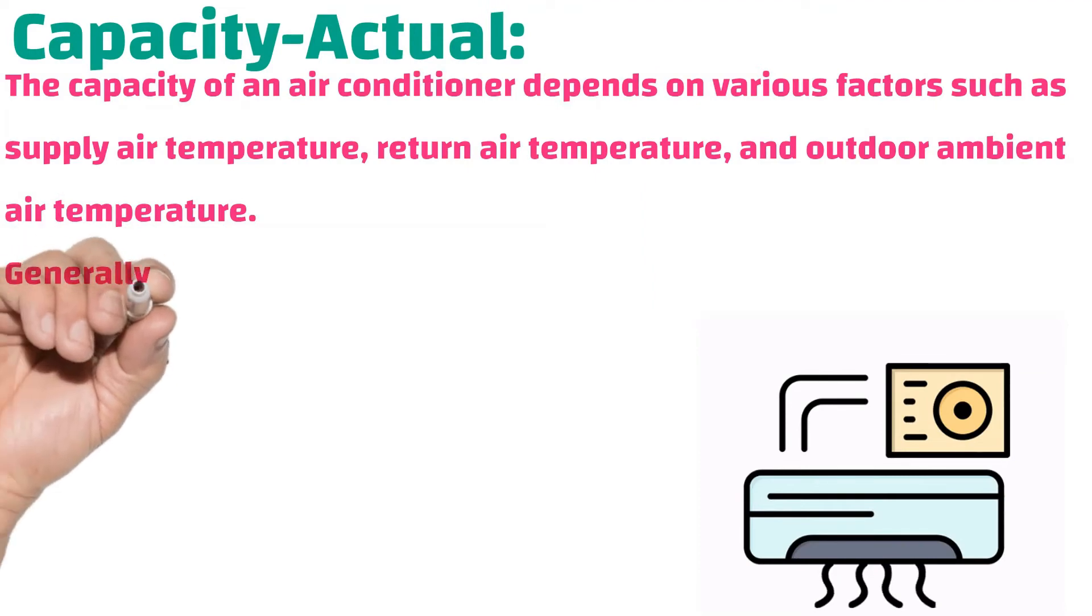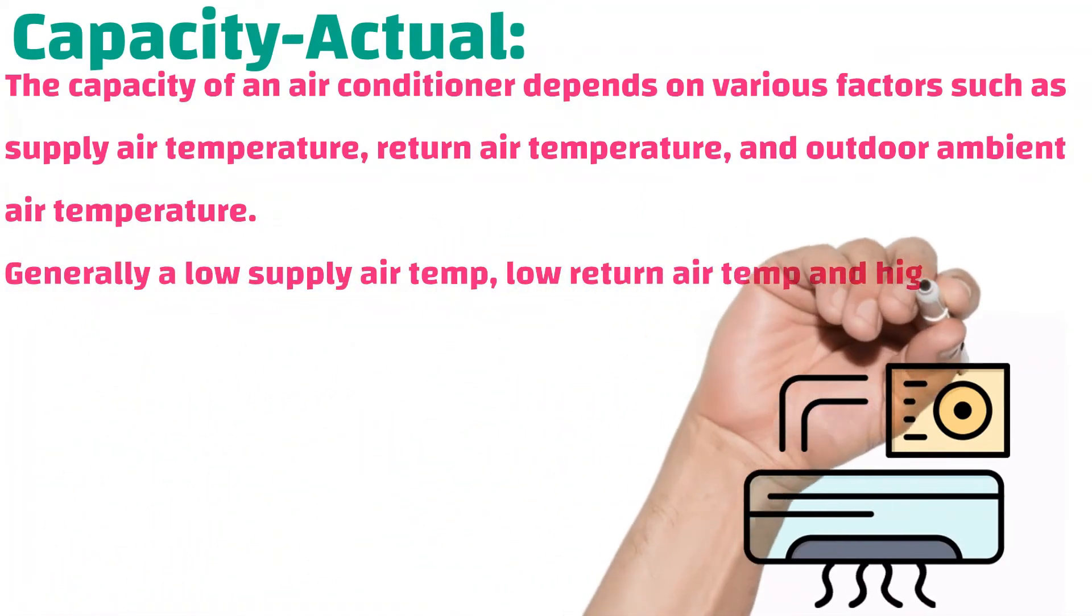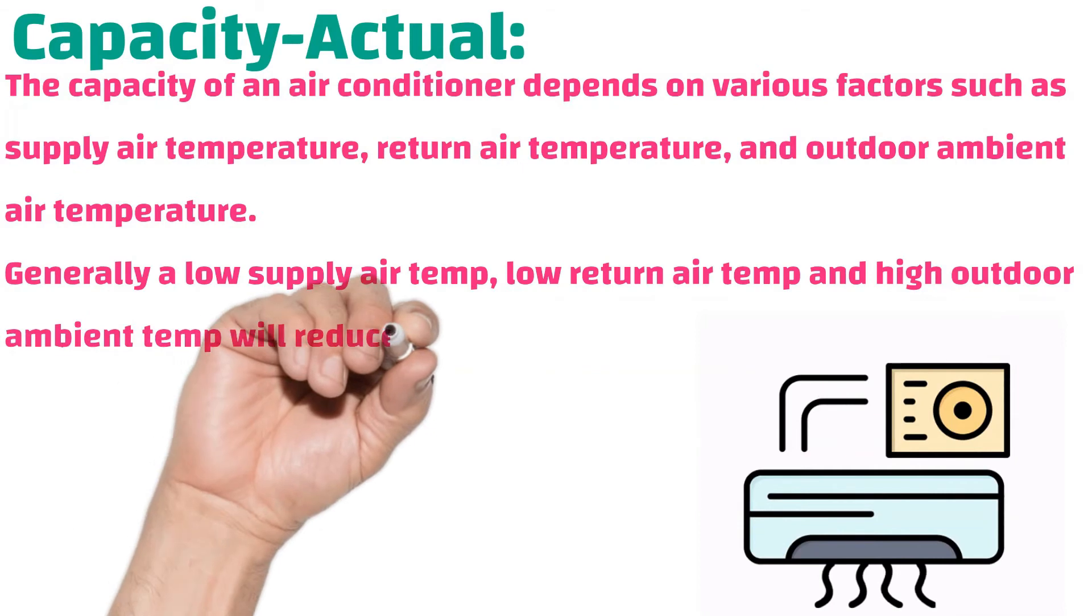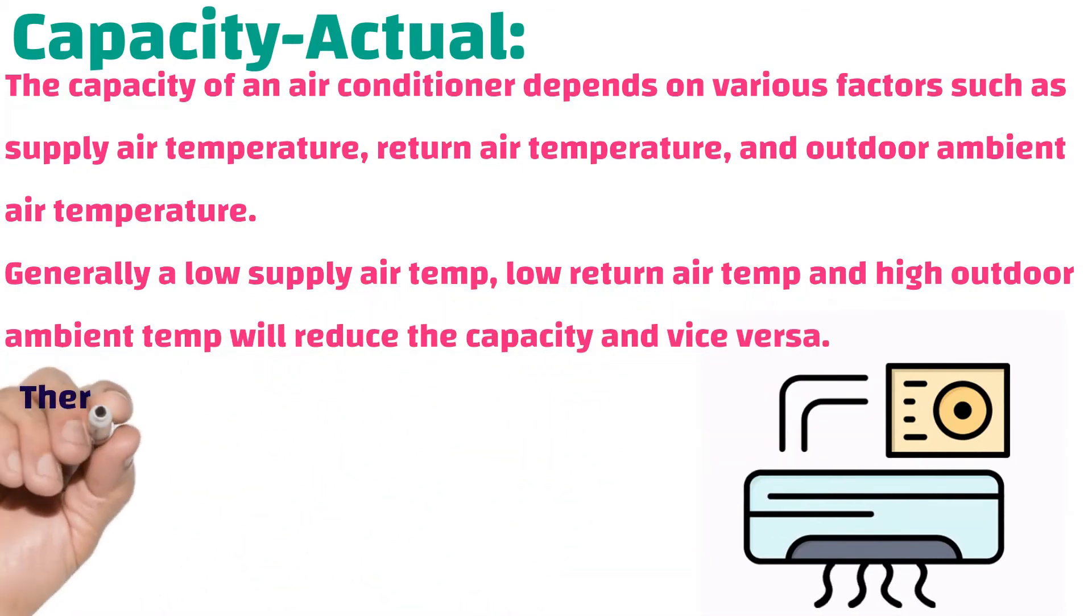Generally a low supply air temperature, low return air temperature, and high outdoor ambient temperature will reduce the capacity, and vice versa.